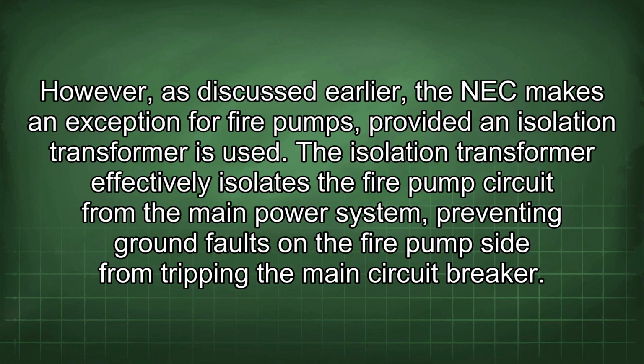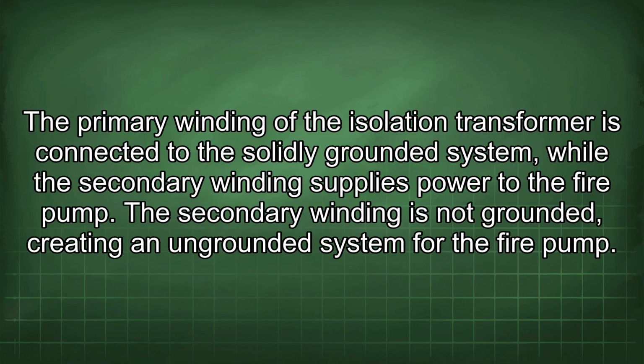However, as discussed earlier, the NEC makes an exception for fire pumps provided an isolation transformer is used. The isolation transformer effectively isolates the fire pump circuit from the main power system, preventing ground faults on the fire pump side from tripping the main circuit breaker. The primary winding of the isolation transformer is connected to the solidly grounded system, while the secondary winding supplies power to the fire pump. The secondary winding is not grounded, creating an ungrounded system for the fire pump.